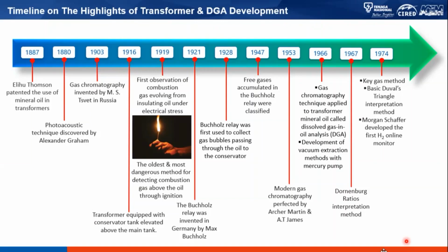If I may relate this to this timeline, from 1919 up to maybe the 1950s to 1960s, most of the research was actually based on the free gases that are generated above the oil, not actually the dissolved gas yet. A very interesting fact is that the first technique people used to test this gas was by igniting a match, which is very, very dangerous, to know whether or not there are gases as the result of a fault within the transformer.